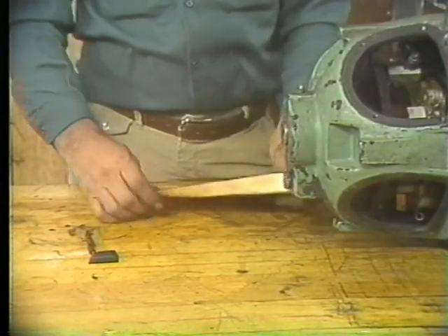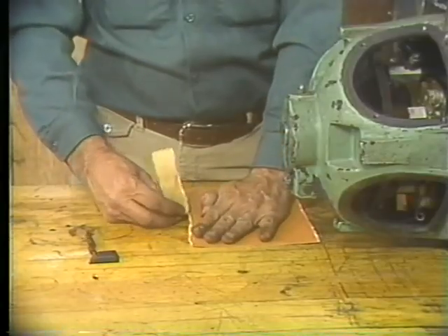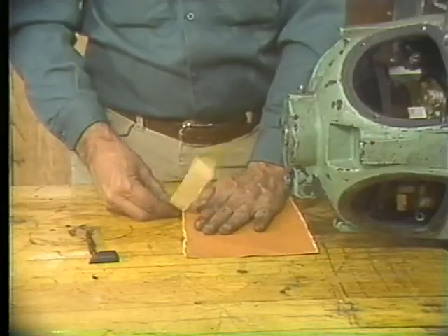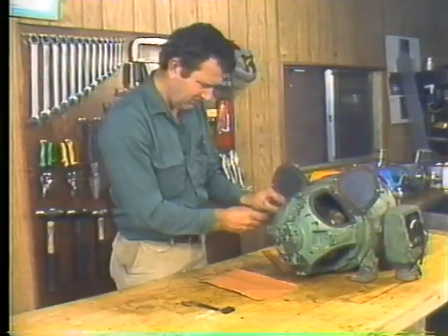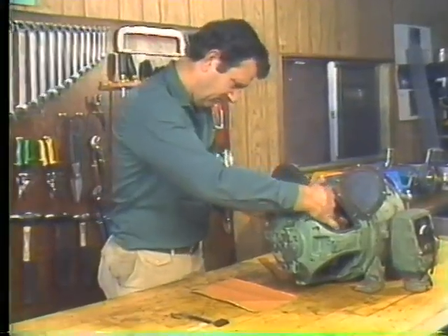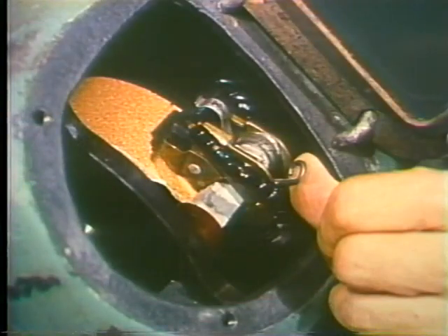Or you'll regret it. You see, emery particles are conductors. If they find their way into the area between the commutator segments, they'll short the motor. Okay? First, you tear a strip from a sheet of flint paper. The strip of flint paper must be at least as wide as the brush to be sure the entire surface is seated. Now place the flint paper on the commutator, flint side out. Then replace the brush and set the tensioning device to hold the brush tightly against the flint paper.